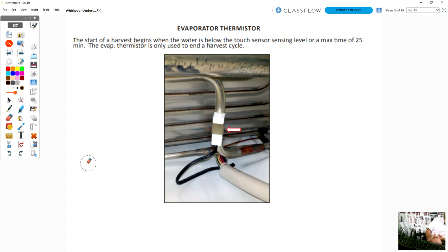Okay, here's where one of the changes has come into play. The older units and the newer units both have an evaporator thermistor. The evaporator thermistor is always on the suction line going back to the compressor. It's sensing the temperature of the refrigerant, and like I said, as ice builds up, we don't pull as much heat. So on the older units, it knows how thick the ice is based on the temperature of the suction line. So if you've got water flowing over the evaporator and the ice is 1 inch thick and it's not dropping, the evaporator thermistor on the older ones is what tells the ice maker to drop ice. On the newer ones, it's the water level sensor that tells the ice maker to drop ice.